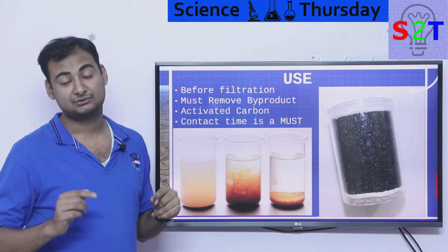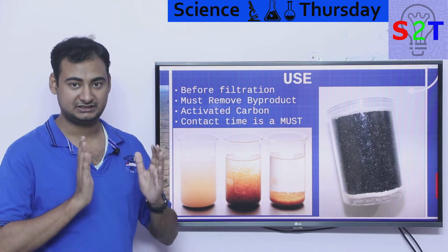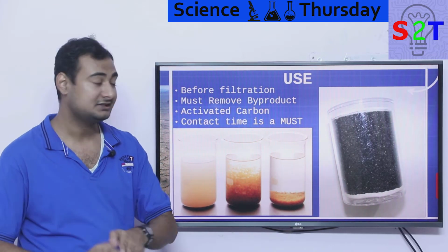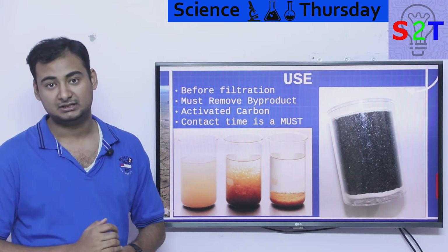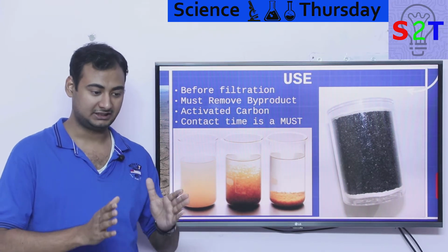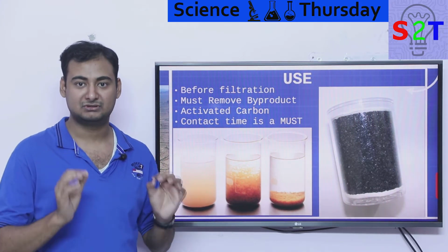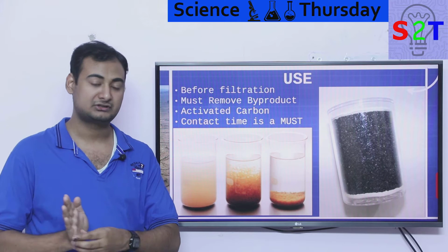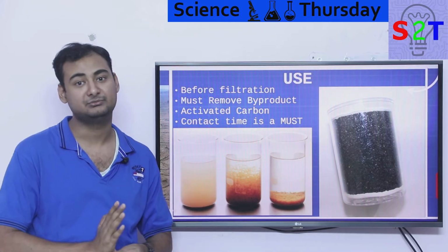Now you have to make sure, in the same way that with UV the radiation exposure must be matched, that in this case contact time is taken care of. Basically they will tell you, okay, for 1 ton of water you must have this much concentration of ozone for at least 15 minutes. You have to make sure of that.